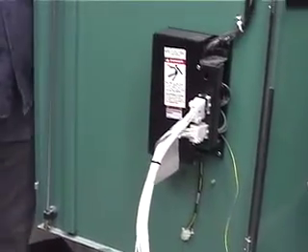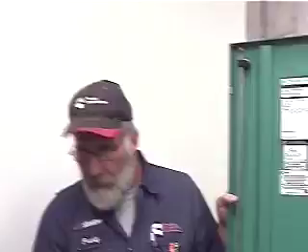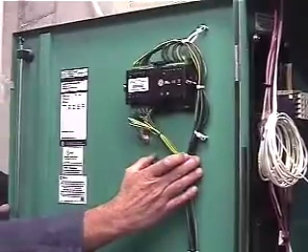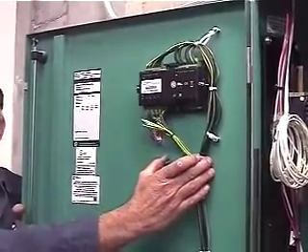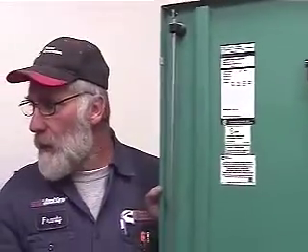This is if you have a battery charger inside here, that we bolt on right here. That one has the same spot for it. Right here is where the little exerciser goes. You can get a programmable exerciser clock for this, $200. You can set it right here and wire it in, and then you can have it do the same thing. Then you have to reprogram this to tell it that you're using an external clock instead of an internal clock. So you guys have to program that with a laptop or something?